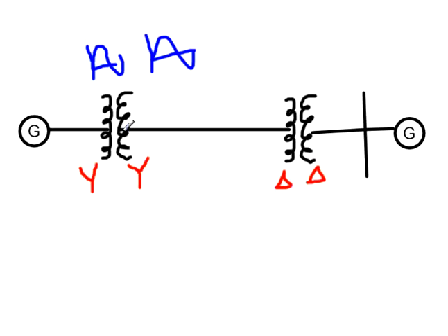There will definitely be a phase shift. The transformer is connected in four ways mainly, in five ways also, but four ways we are using: star star, star delta, delta star and delta delta. So the four connections will be used, and one more, the star zigzag connection, will be used rarely. For the delta delta connection or star star connection, there is no phase shift.